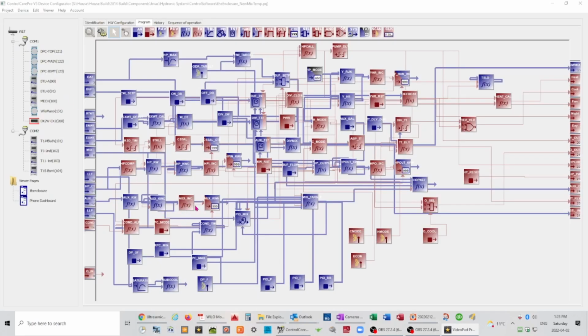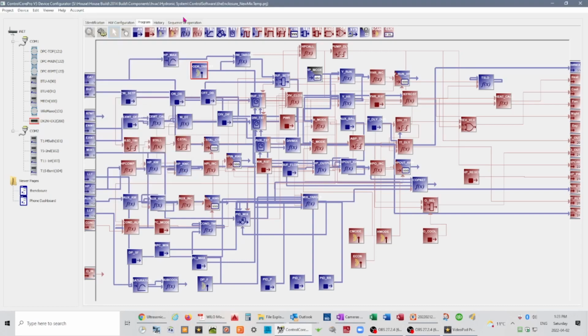So now let's go to one of those formulas, and let's talk about the mixing temp. So in a good, well-designed system, the temperature that you are maintaining in the buffer tank and in the main circuit going to the house is based on the difference between indoor temperature and outdoor temperature. So the colder the outside gets, the higher the heating load, therefore you require a higher heating temperature.